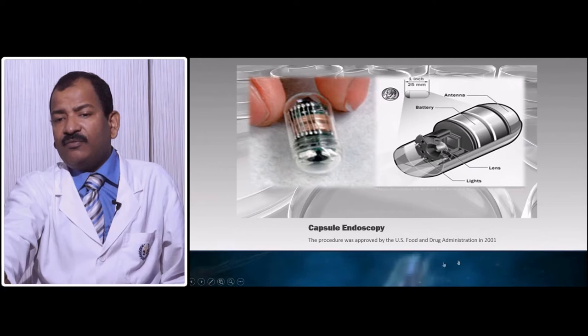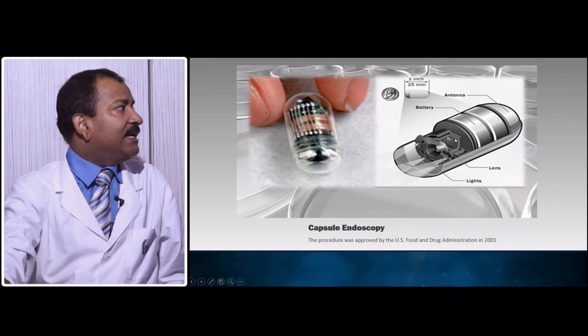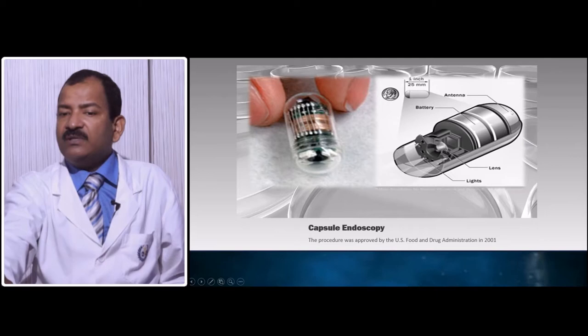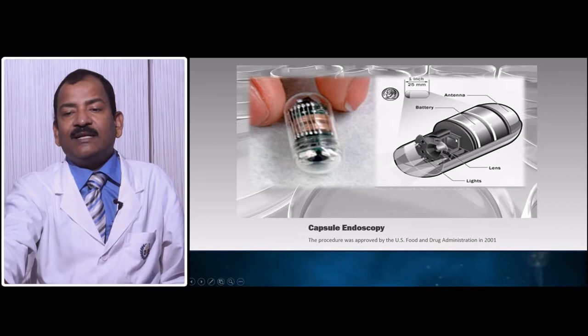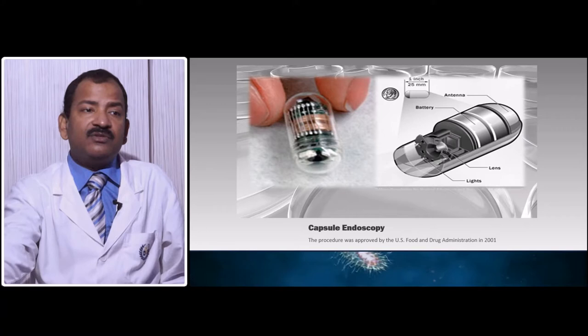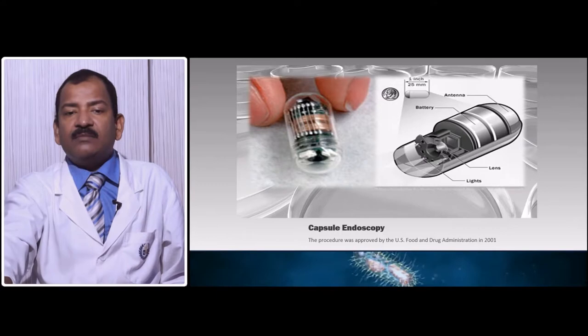The capsule endoscope has a lens that projects the image to a CCD (charge-coupled device), LED lights on the periphery, two batteries, and one antenna. Once dropped inside, the light switches on, the image goes to the lens, the lens focuses the image to the CCD, and via Bluetooth or wireless technology the image is sent outside or memorized. Once the patient passes the capsule in the fecal matter, you can retrieve and examine it.